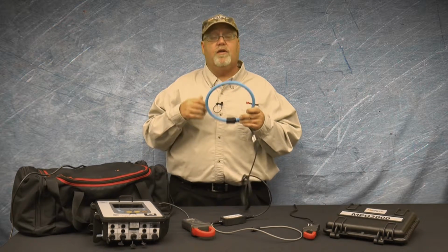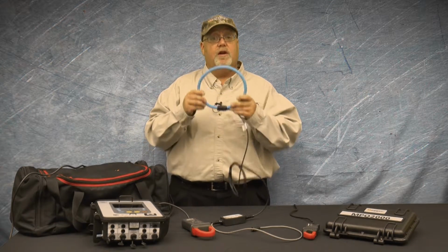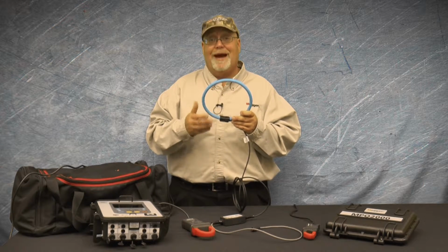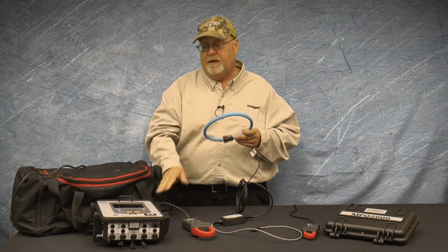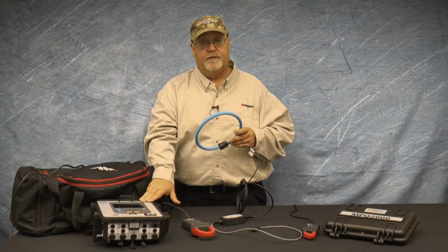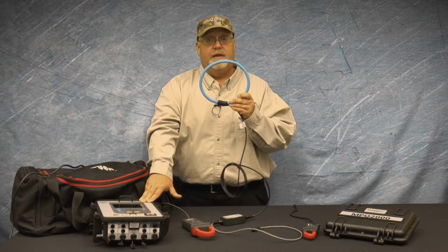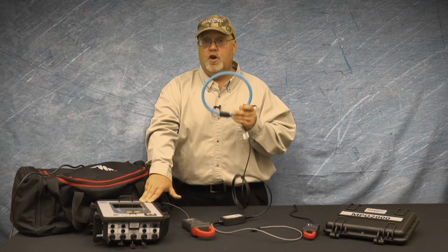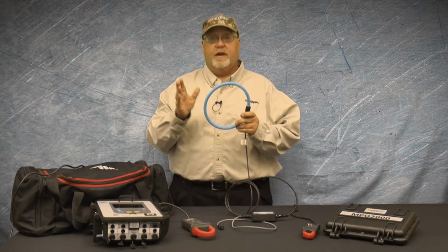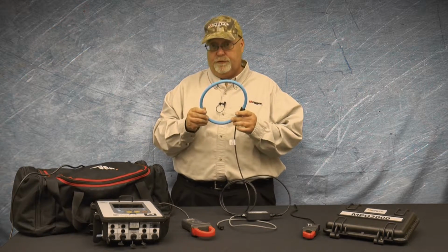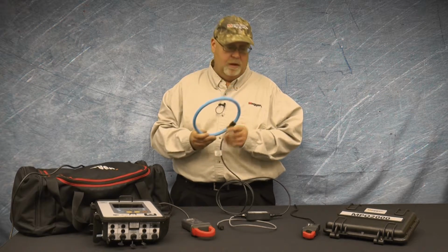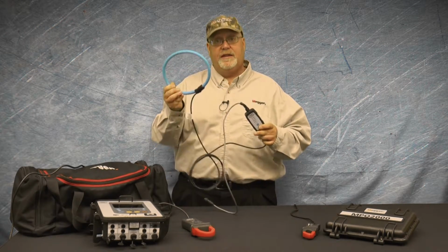Since the signals require integration, this means the Rogowski coils require power. So many Rogowski coils require batteries to operate. The Megger line of power quality analyzers will power the Megger line of flexible CTs, so ours require no batteries. Rogowski coils do not have iron cores that can saturate. So, by alternating the gain stages, we can create CTs that have multiple ranges.